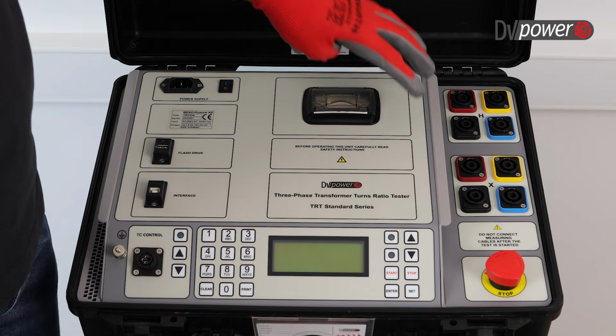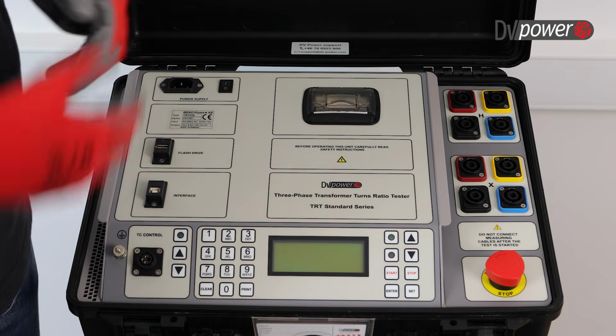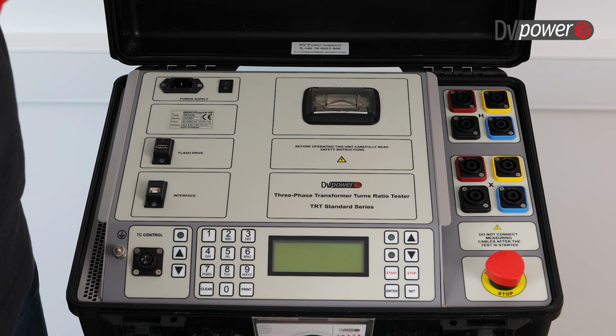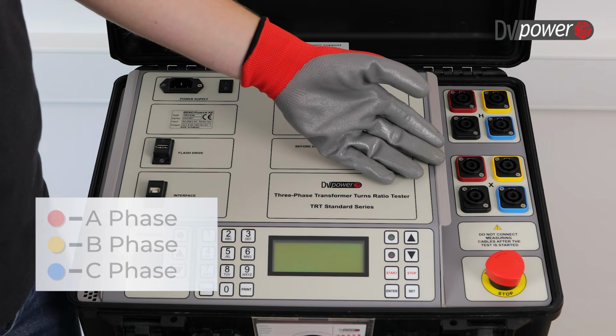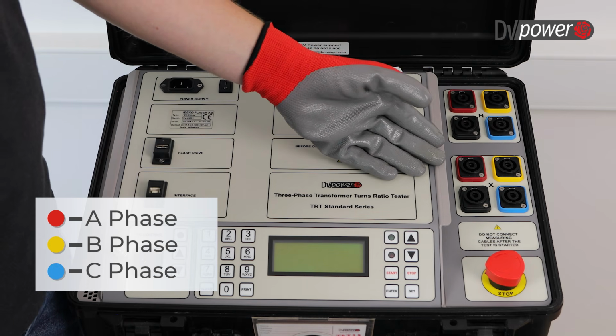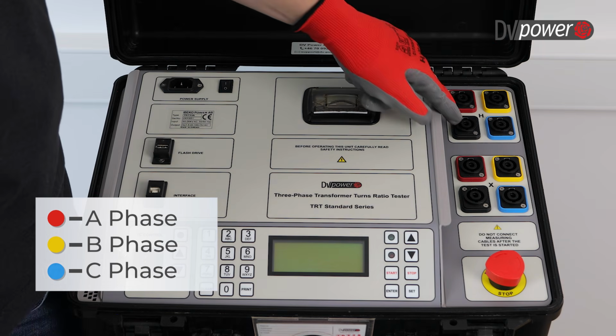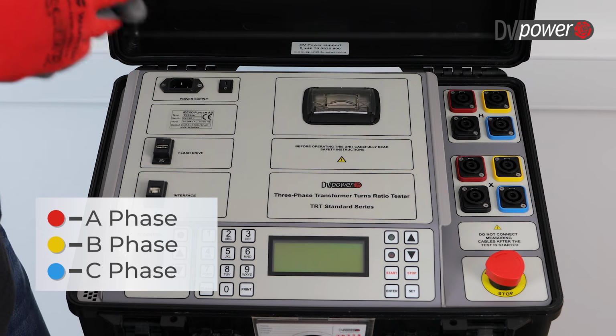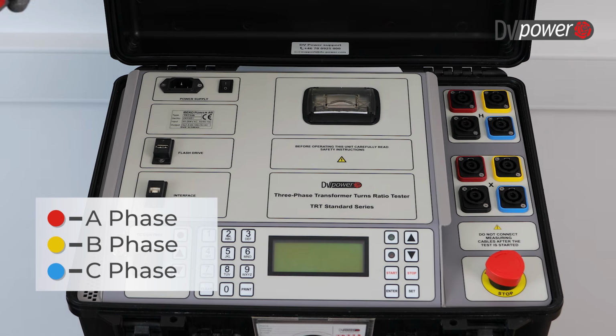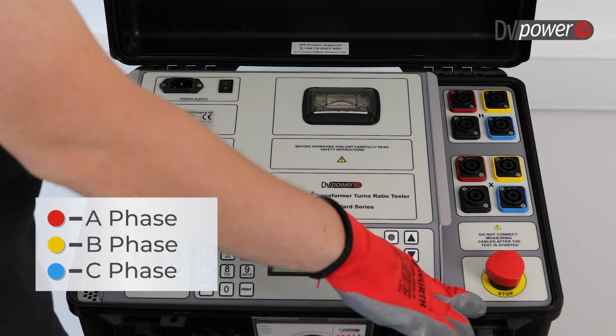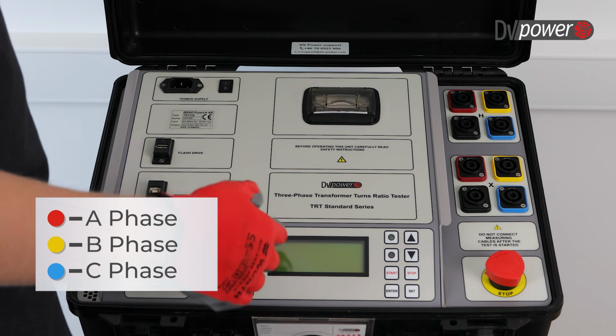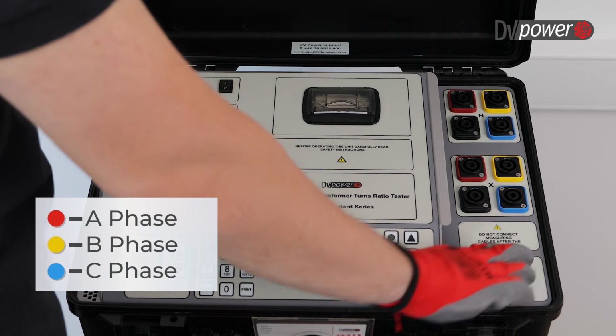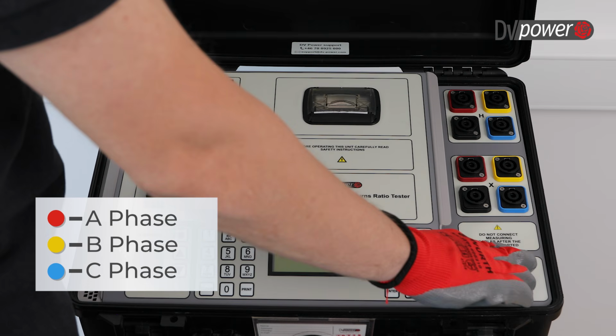On the right hand side of the device you can see 8 terminals. 4 of them are dedicated for connection of cables for the high voltage side, and 4 of them are there for connection of the cables to the low voltage side. 3 of them represent connectors for A, B and C phases, and the 4th one, the black one, is for connection to the neutral point of the transformer if one is present. Emergency stop button is also there. The name is self-explanatory, only used in emergency situations. After pressing the emergency stop button, all the running tests would be terminated.